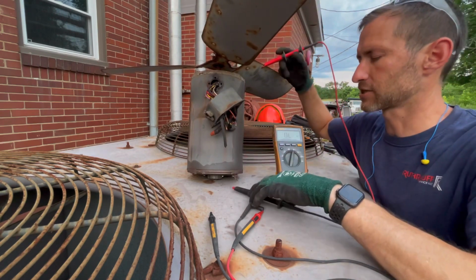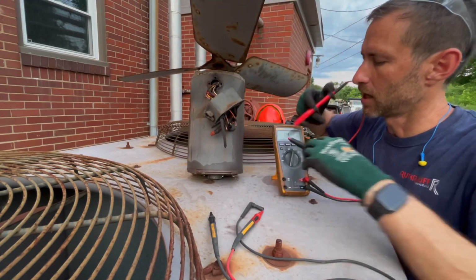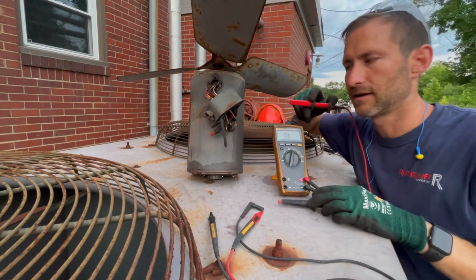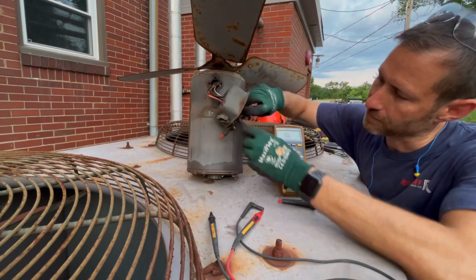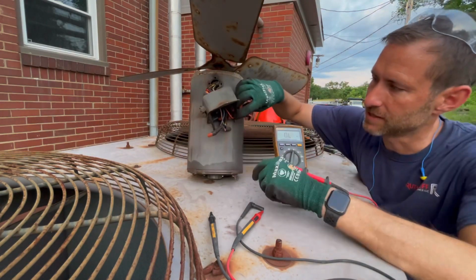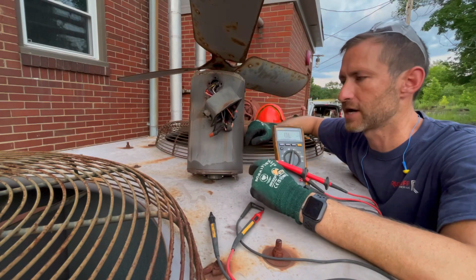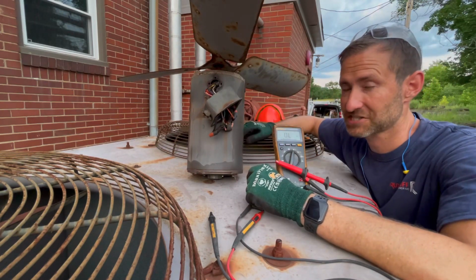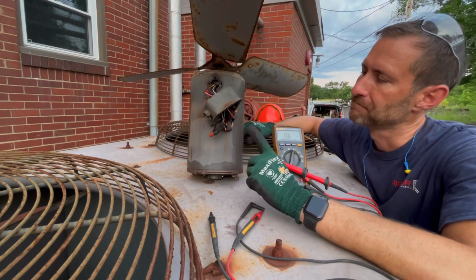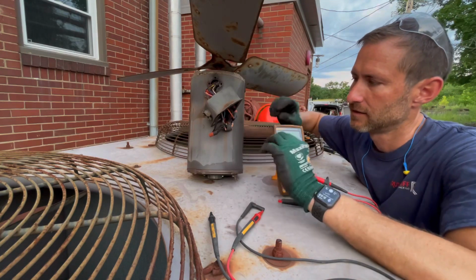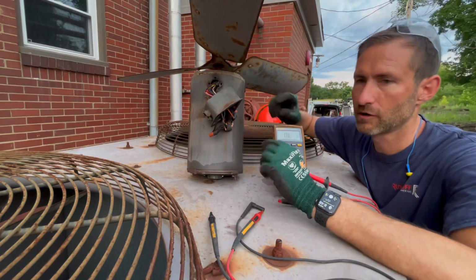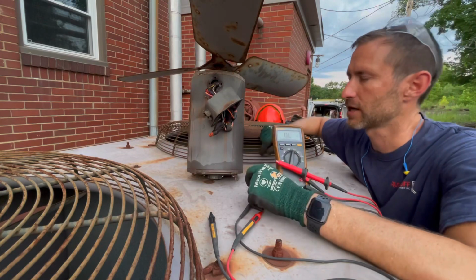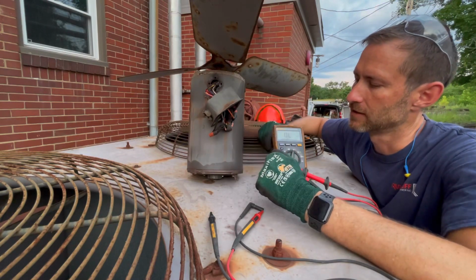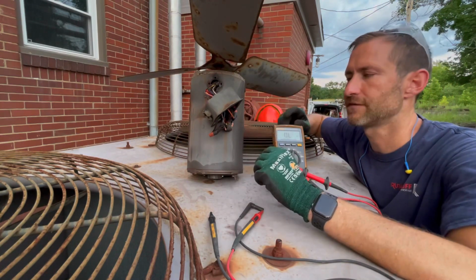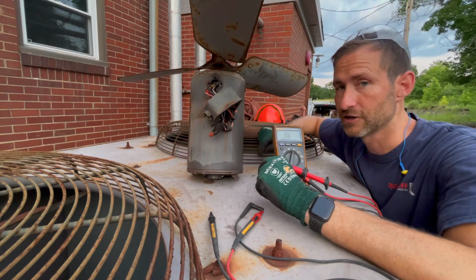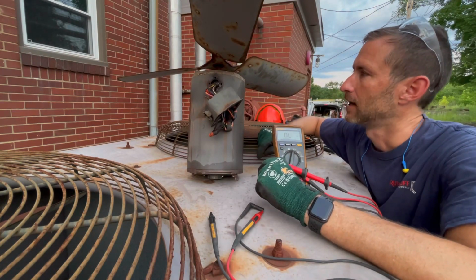Well anyways, that's grounded. So if you're reading a resistance between ground and the copper, that means that copper is doing this - it's grounded, people. That'll blow a fuse, trip a breaker, go poof. It's scary, it's a scary noise. Reading open means those windings - it's not coiled together to start that motor in that correct rotation, so it's open. You should be reading a resistance. If it's three-phase, they should be identical between all three. So okay guys, remember that.